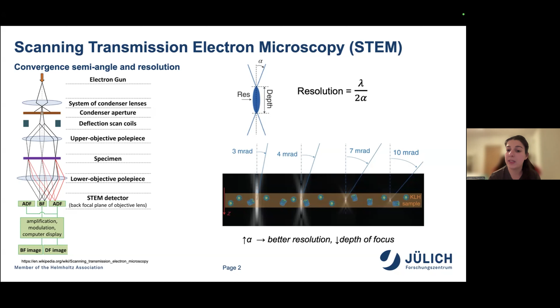But an important parameter to form our probe and its geometry is the convergence semi-angle, the alpha that you can see here. With that, we are able to fix the depth of focus, and also it's related with the maximal theoretical resolution that we can reach. As we are opening our convergence semi-angle, our probe, we are decreasing the depth of focus, and then we can reach higher resolutions.